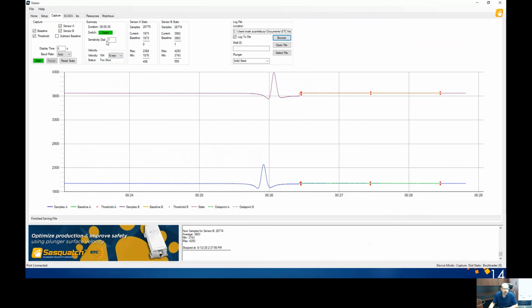Some things that you can see here, the switch goes back to open. It was closed when it triggered. Once again, the sensitivity dial setting. We have a velocity number. I ran it below the range of this sensor, but if you move a screwdriver or a plunger by it more quickly, you'll see the different velocities come by here. We've also got some stats of the types of samples it's reading and the mins and the maxes and the baseline. So what you see here is sensor A and sensor B, baseline, threshold. So you can start and stop it. You can also log this to a file. So if you want to record this data for later, you can.